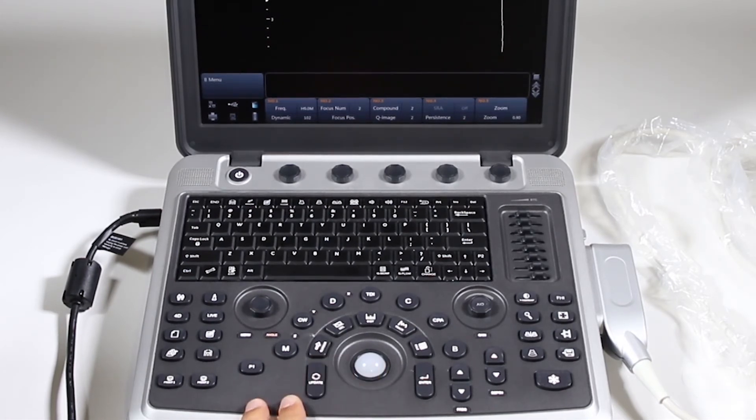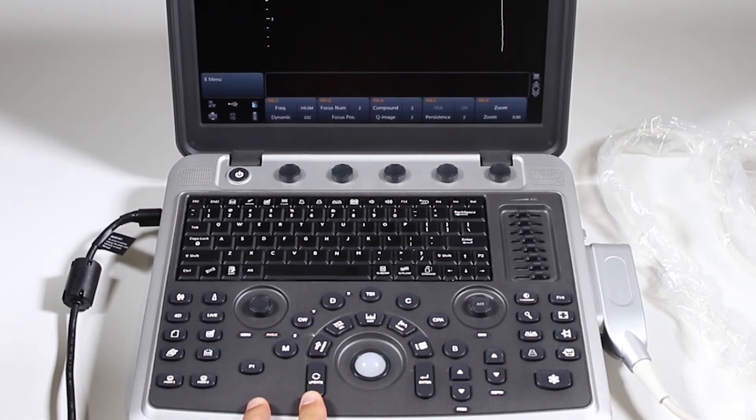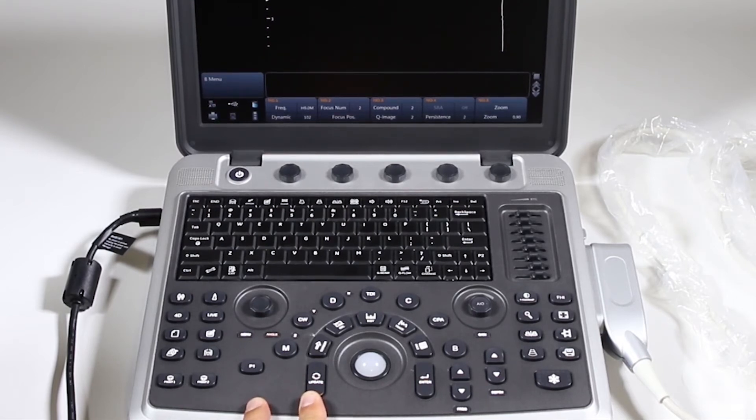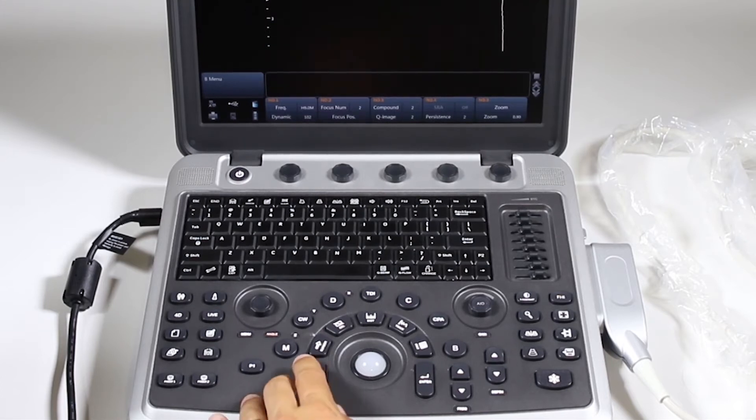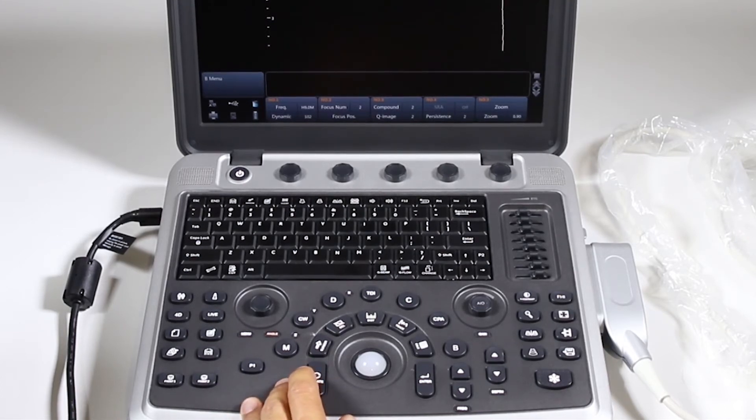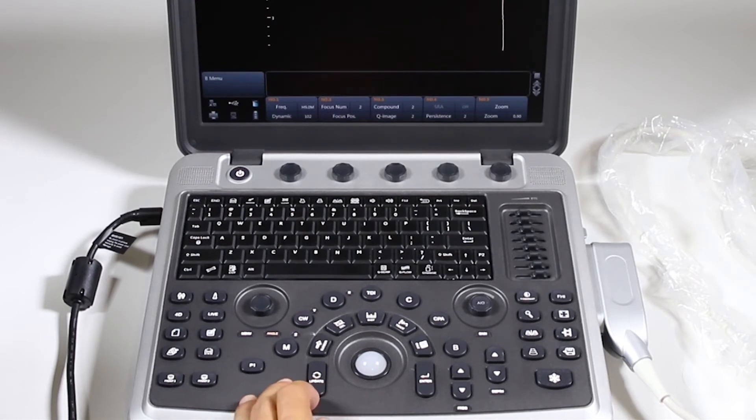Of course, you have your trackball here. Update will apply to multiple functions, making PW Doppler live and sometimes making some measurements that allow you to change the width of an ellipse or maybe the placement of the cursor.